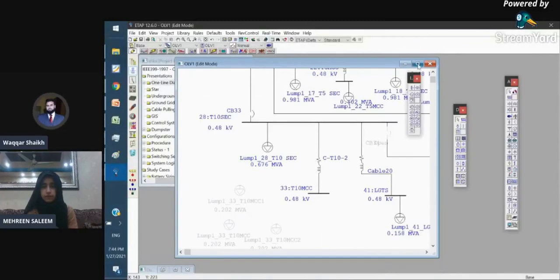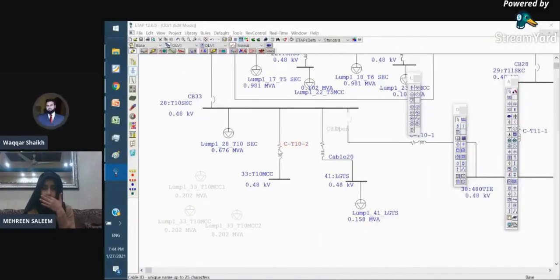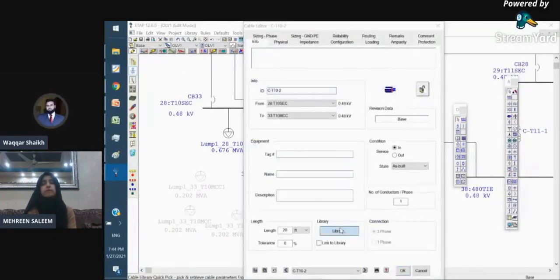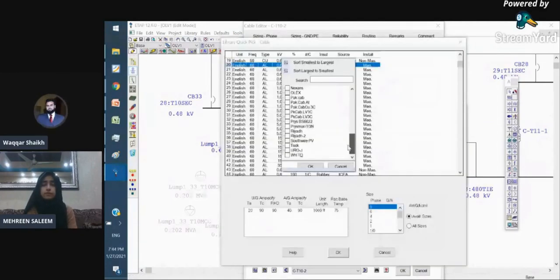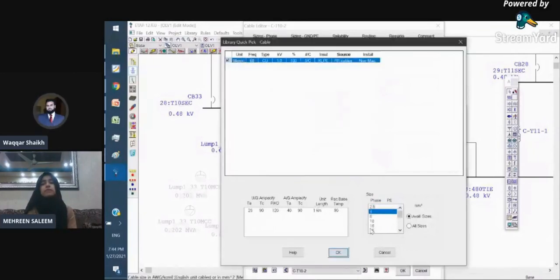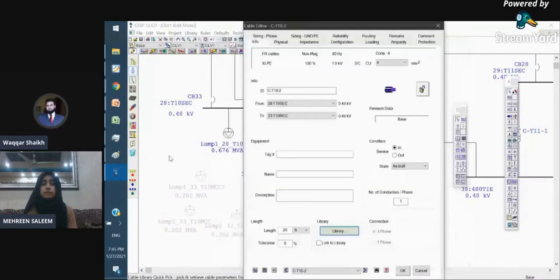Now if I go back into the cables library and filter my manufacturer, you will find FR cables listed over here. If I select this FR cable and select 4 mm square cable here, it would give me the same ampacity that I have input into the software. It would take into consideration the same resistance and reactance values already input into the ETAP database. So this is the way we can model the cables into the ETAP library.